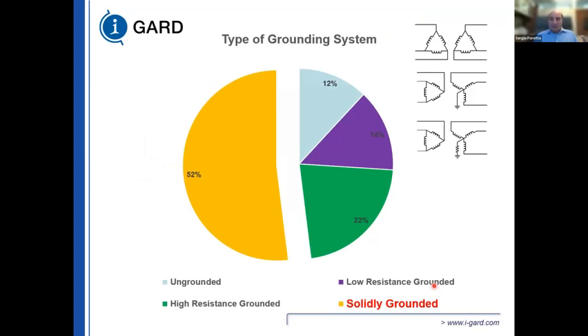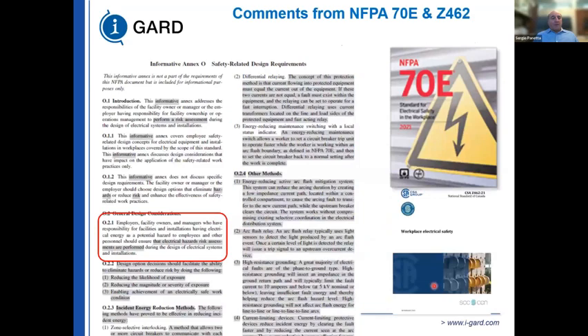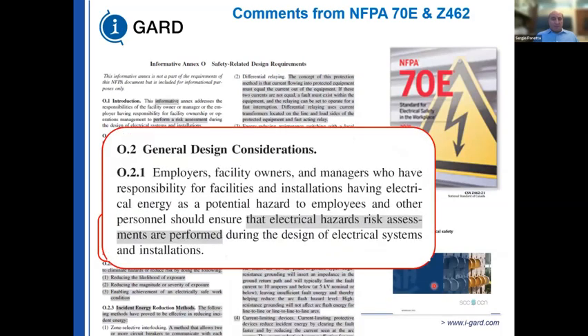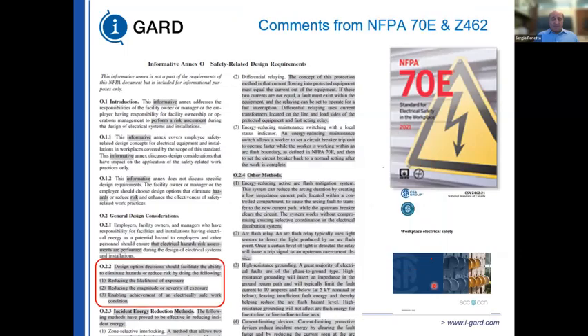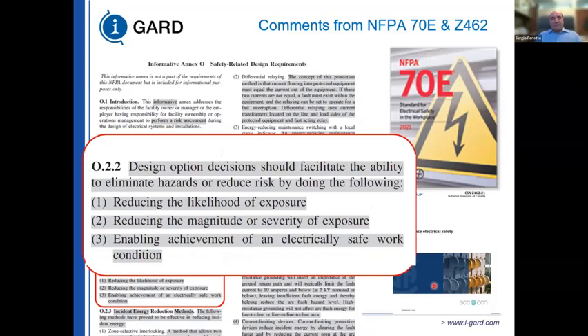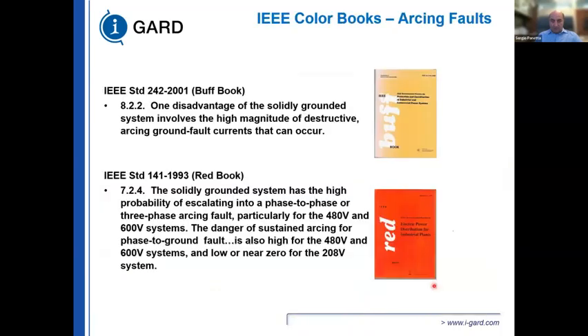So we're going to discuss solidly grounded systems now. So NFPA 70E and CSA Z462 say that employers, facility owners, and managers who have responsibility for facilities and installations having electrical energy as a potential hazard to employees and other personnel should ensure that electrical hazard risk assessments are performed during the design and operation of the system. So the risk assessment involves three things: reducing the likelihood of exposure to a ground fault, reducing the magnitude or severity of exposure, and enabling achievement of an electrical safe work condition.